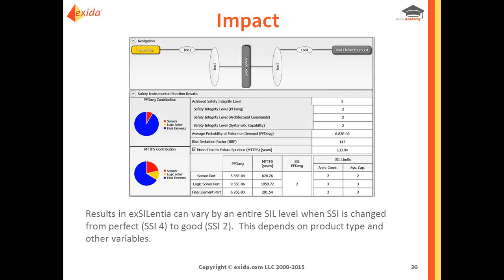And then once again, what is the impact? Results in exSILentia can vary by an entire SIL level when SSI is changed from an SSI 4 to an SSI 2. People say, oh, I'm operating at a SIL 3, but in reality, if your processes are in place and you're not following your proof tests, and you're a little slow, you're delaying things, you actually might be operating at a whole SIL level less. So keep that in mind.